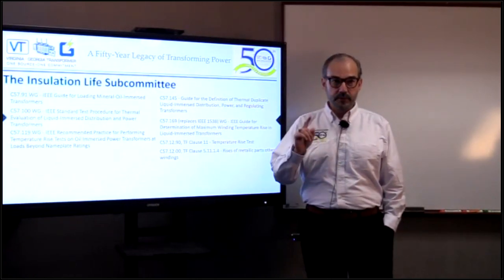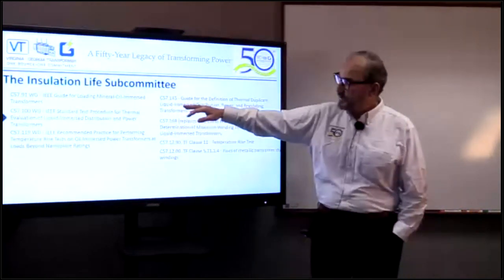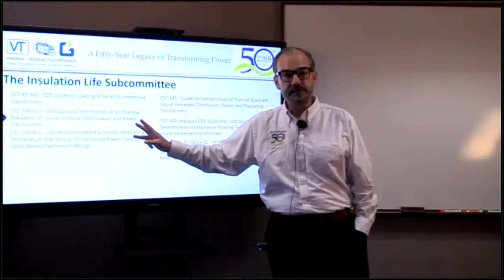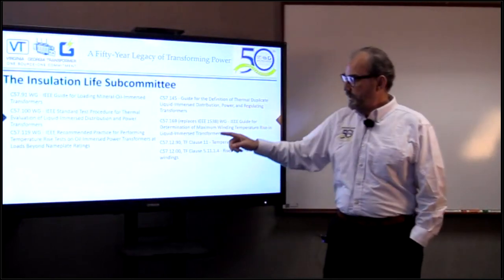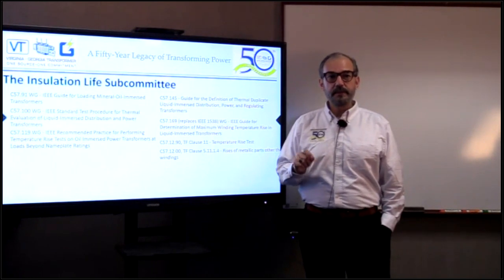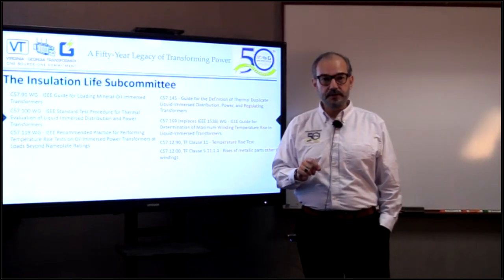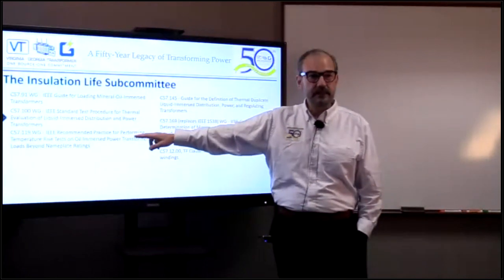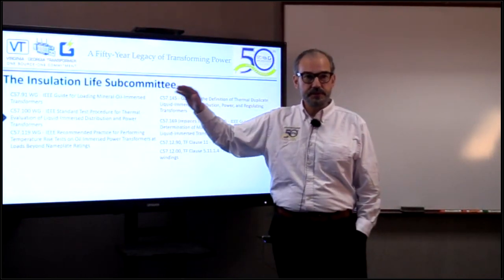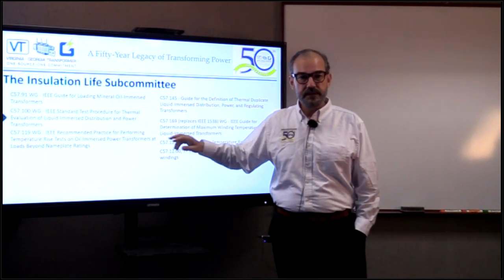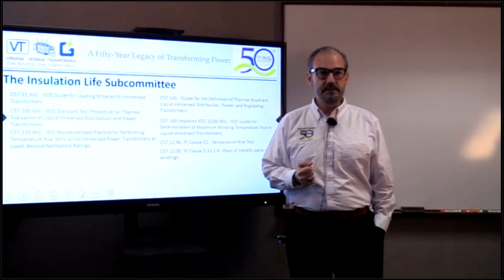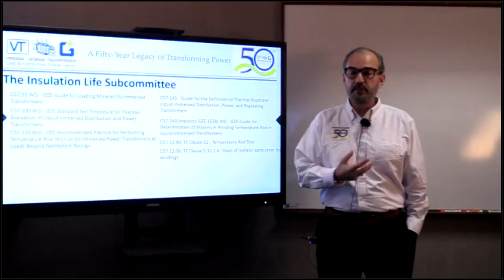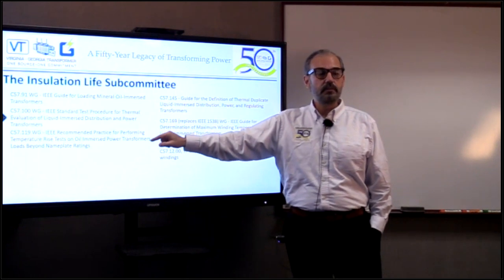Under the insulation life subcommittee, C57.91 is the guide for loading mineral oil-immersed transformers — the loading guide most people have heard of, covering the loading of transformers relative to ambient temperatures and many other aspects. C57.100 is the standard test procedure for thermal evaluation of liquid-immersed distribution and power transformers. C57.119 is the recommended practice for performing temperature rise tests on oil-immersed power transformers at loads beyond nameplate ratings.